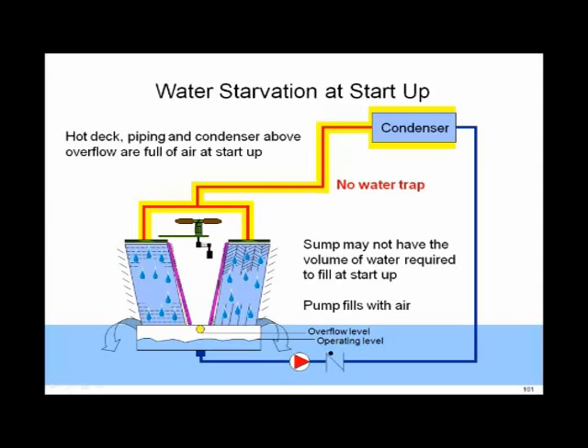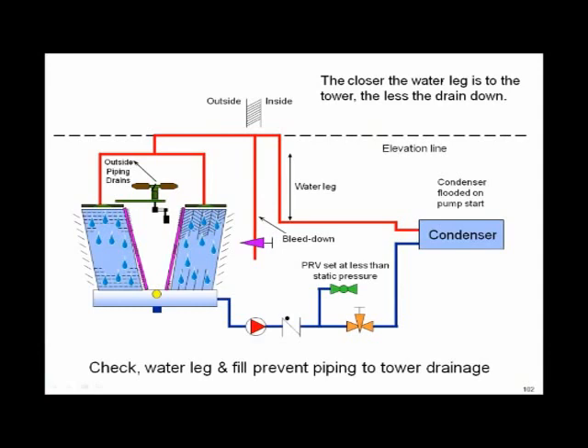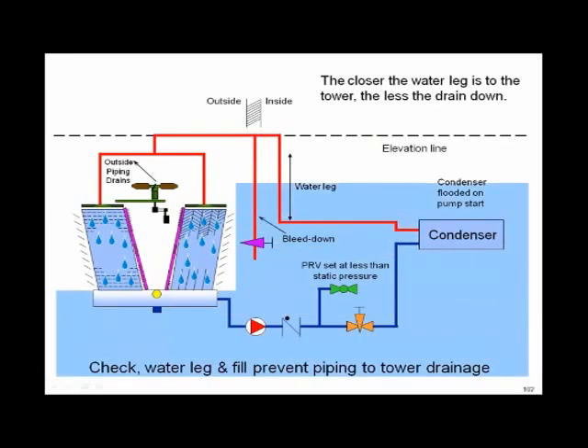What's the solution to those two problems? A water trap. Remember that water trap, if you do it properly, out close to the tower. It's just a piece of vertical pipe running up above the tower to make sure you trap the water in the condenser and the horizontal piping. When you turn the pump off, as you recall earlier, it traps the water at that point, and you stop the overflow. Water going out the parking lot, you stop the overflow. And when you turn the pump back on, you also stop it from pumping everything down and starving it.